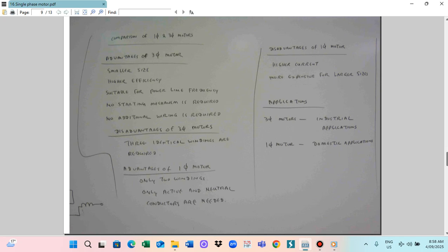Winding resistance is very important in the three-phase winding, so you have to measure the three-phase winding resistance. If the resistances are significantly different, the three-phase machine cannot run properly. This is the point where three-phase machines are at a disadvantage compared with the single-phase motor.